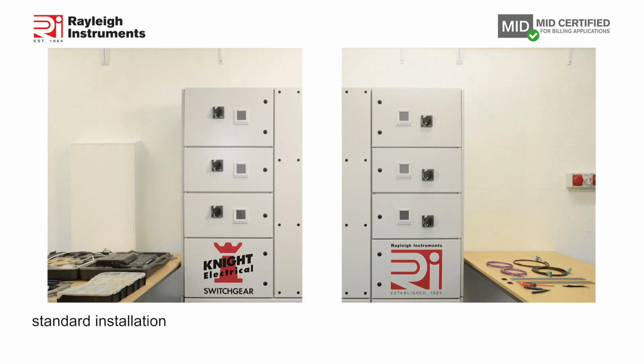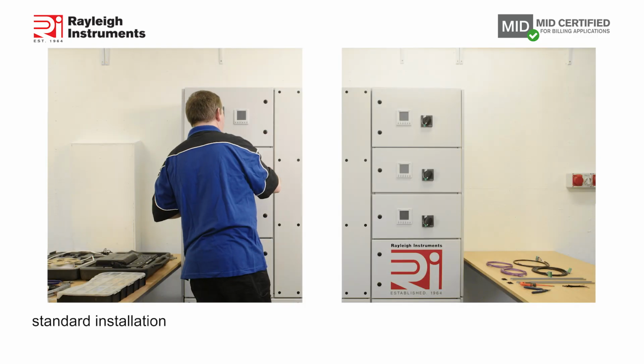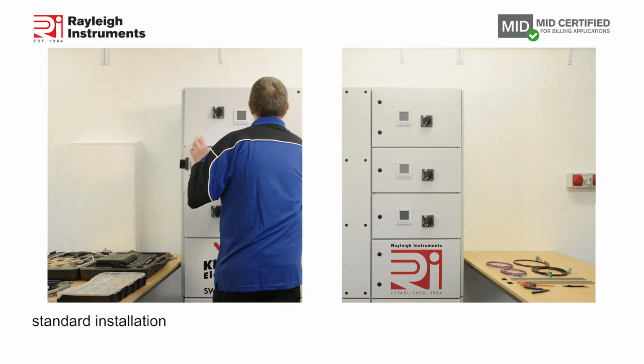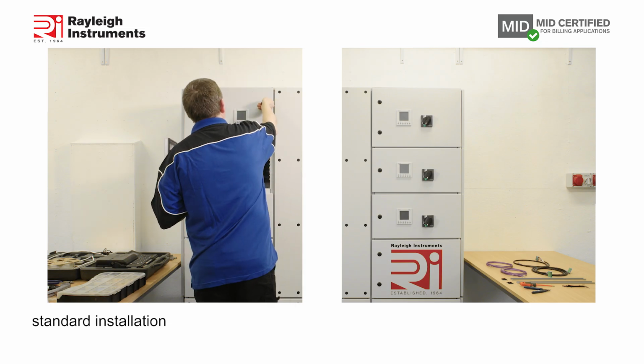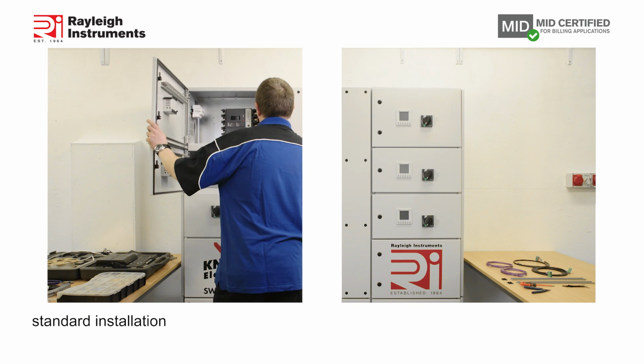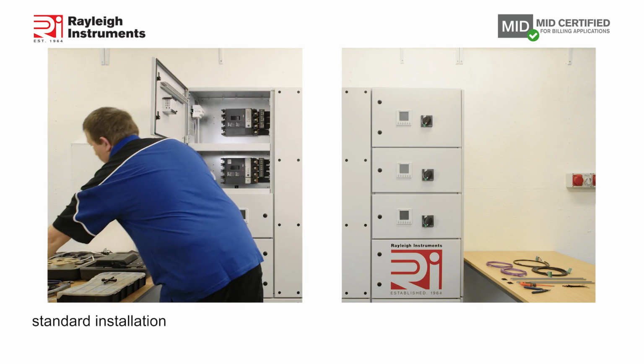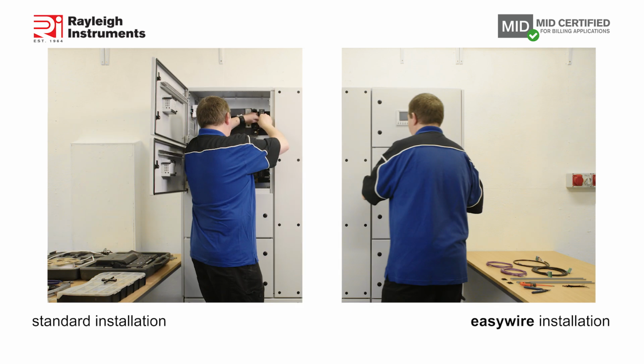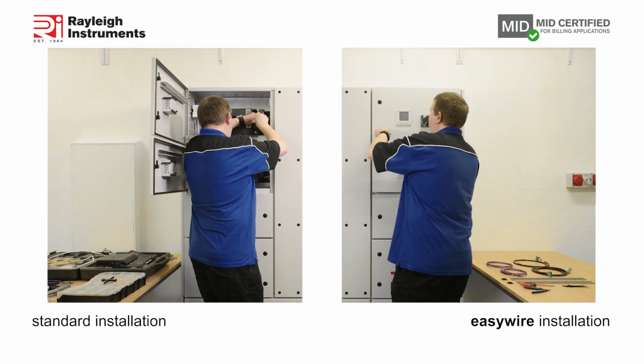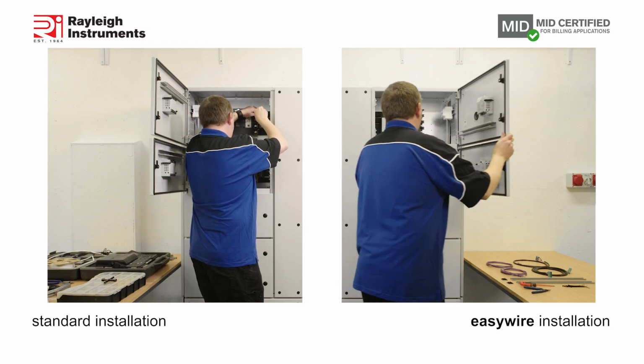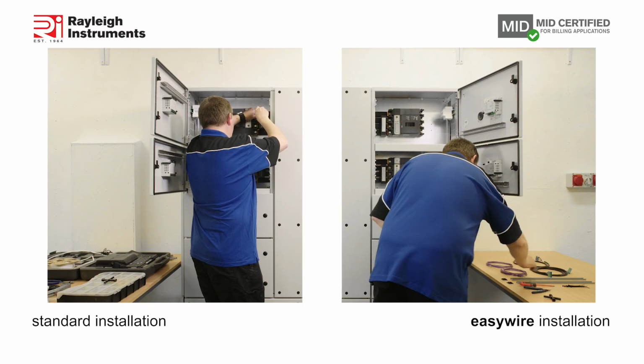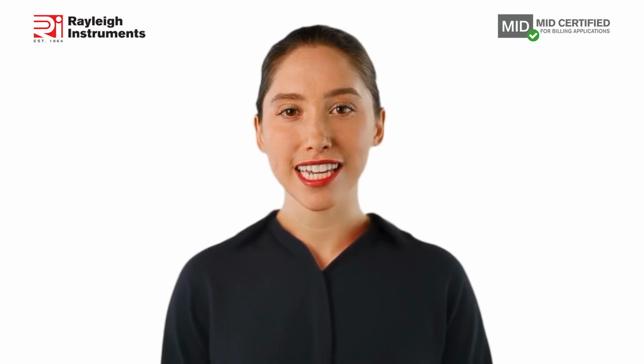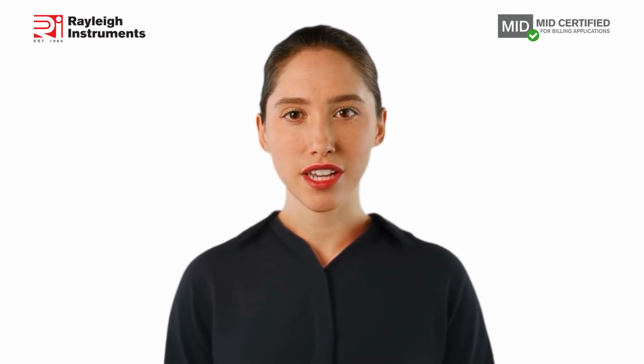Here, on the left, we look at a typical installation fitting 2 standard multifunction panel meters and 2 standard 3-phase current transformers, including all the cable cutting, cable labeling, and the fitting of ferrules. On the right, we see the fitting of 2 Easywire multifunction energy meters and 2 Easywire 3-phase current transformers.